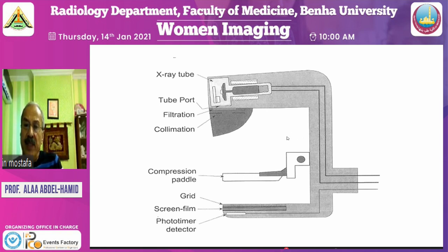The design of the tube, here the tube housing, this is the cathode and this is the anode. As you see here, there is a bevel in the anode in order to redirect the X-ray beam downward. And then we have a tube port, the filter use, we explain it, and the collimation. Collimation is manually controlled, and you can get the aperture width as you need. And then the compression paddle. Compression bevel is very important in order to fix the breast. And then the film housing, composed of the grid, screen film, photo timer present here at the lower part of the film housing.